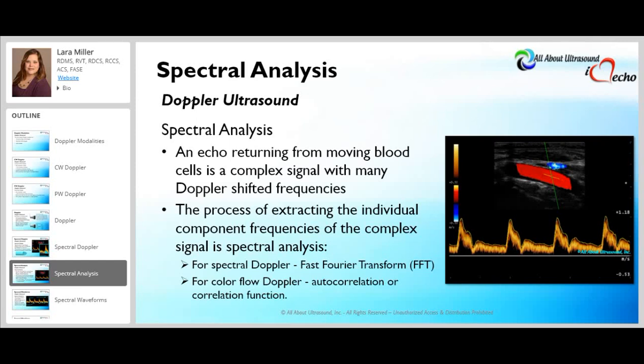Autocorrelation with color Doppler is used because of the vast amount of Doppler information that needs to be processed. It is a little less accurate than spectral Doppler and fast Fourier transform; however, it is much faster.